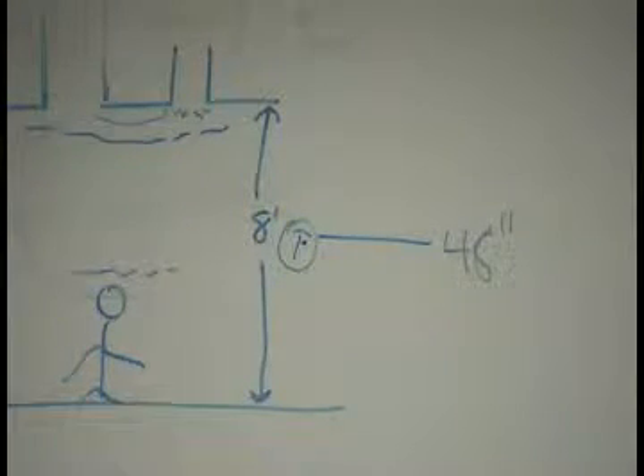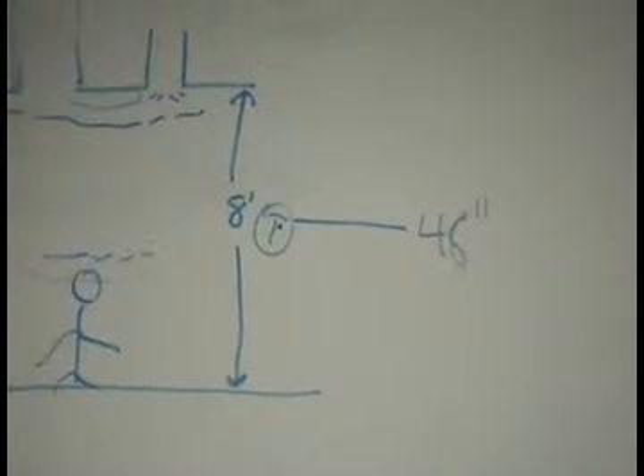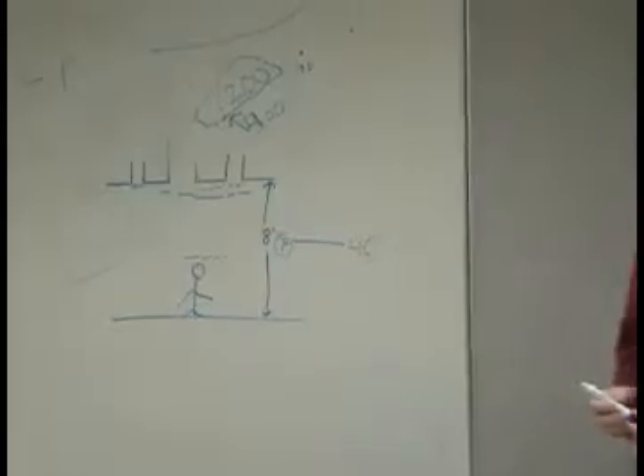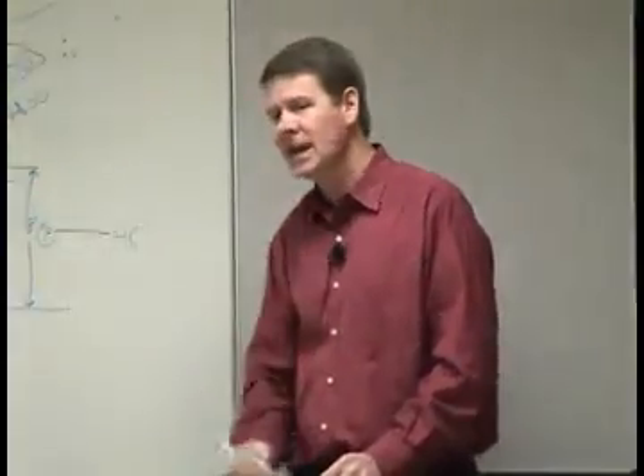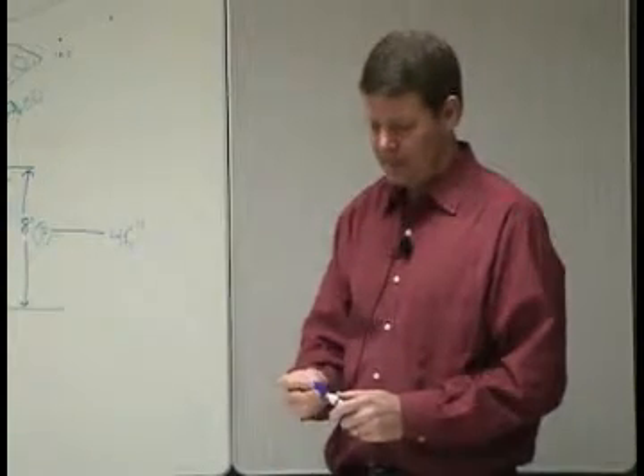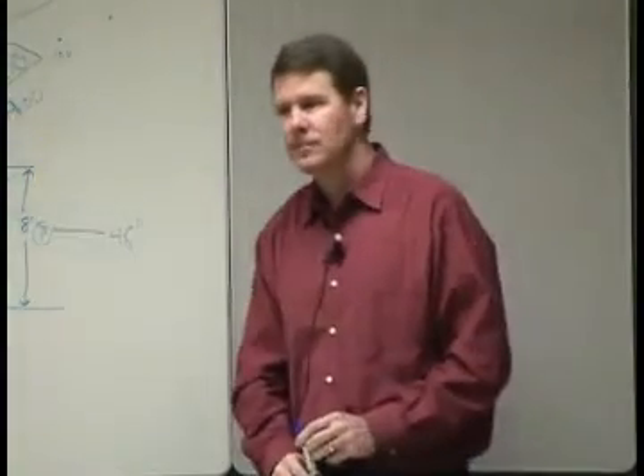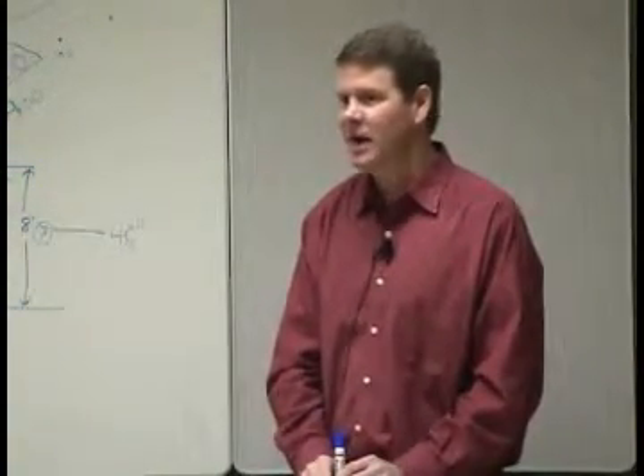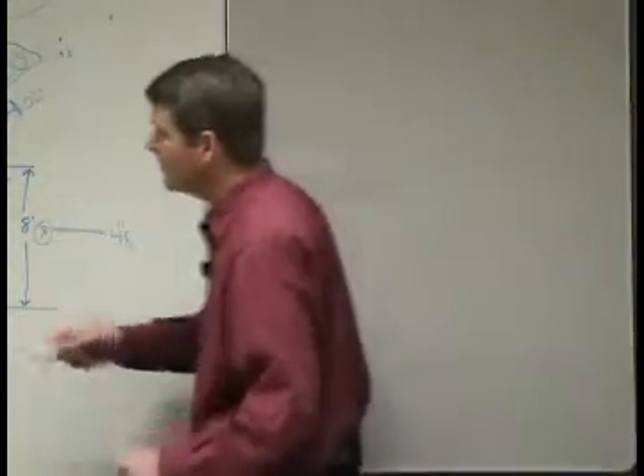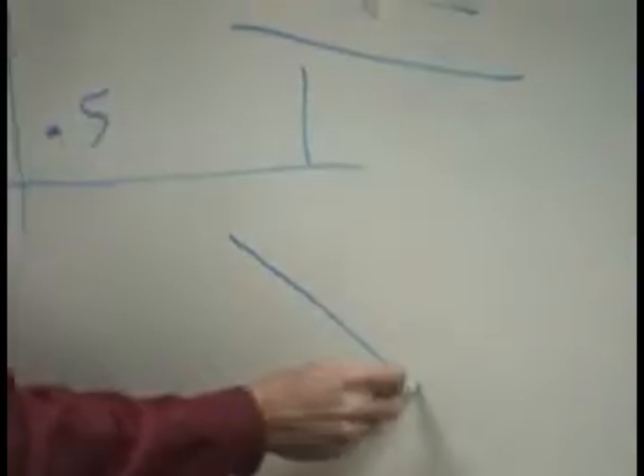Rooms that are difficult to heat, if you've got a lot of windows, you're on a north face, you're going to have this all the time. And so you either got to raise your minimum up, or we'll often now program it such that we will raise the CFM back up to whatever in order to get throw out of the registers and get some heat down off them. Program it based on the continuing fall in space temperature, do you program it based on time, or? The temperature. If that temperature doesn't come up, then, so we'll kind of do one of these. As our temperature drops, our CFM will go down, get to where our minimum is. We'll start opening our valve up.